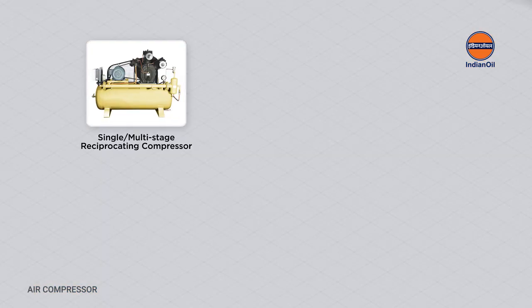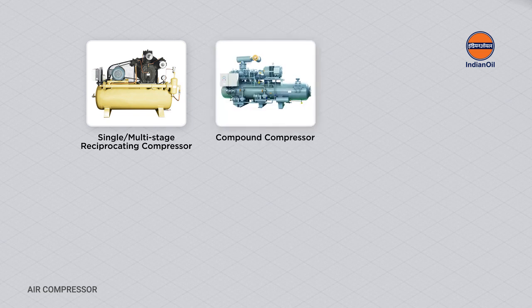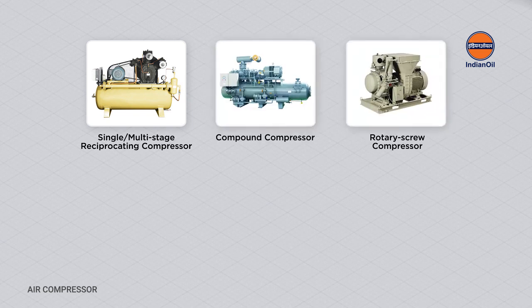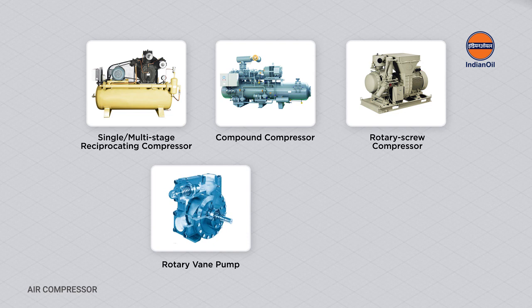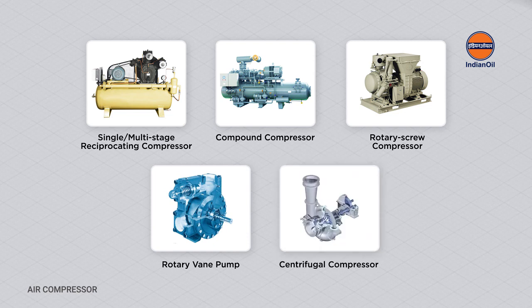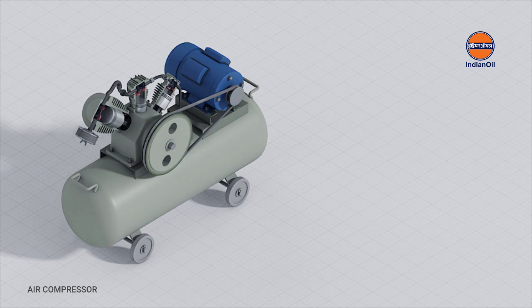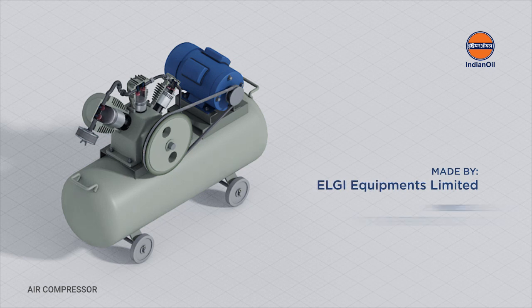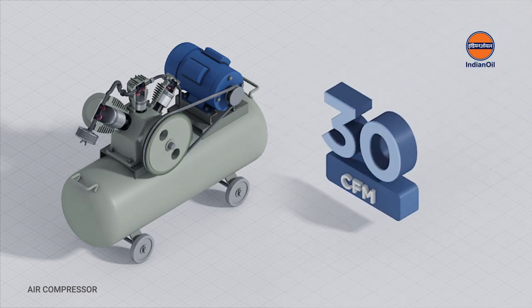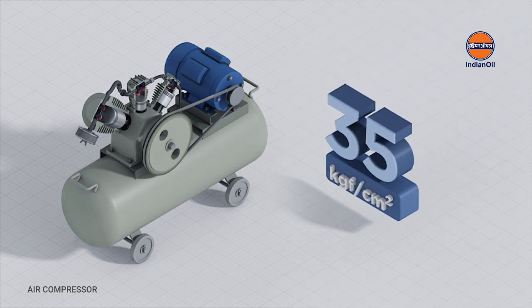Types include: single or multi-stage reciprocating compressor, compound compressor, rotary screw compressor, rotary vane pump, and centrifugal compressor. This is an example of a three-stage reciprocating compressor made by ELGI Equipments Limited — a THPC 1500T model designed to supply compressed air at a flow of 30 CFM, 0.85 M3 per minute, at a pressure of 35 kgf per centimeter square.